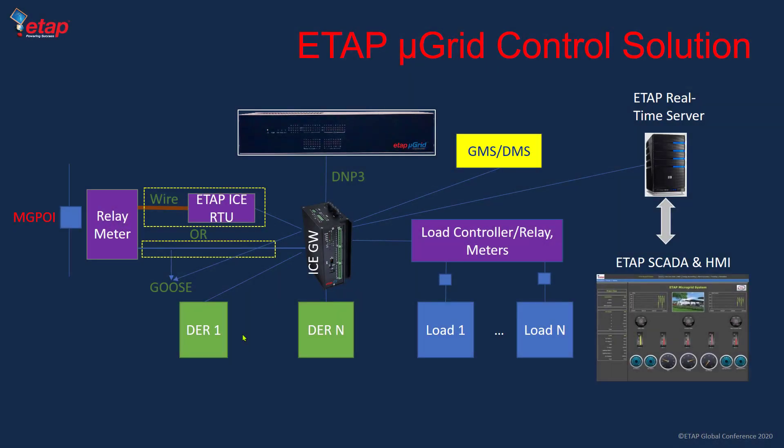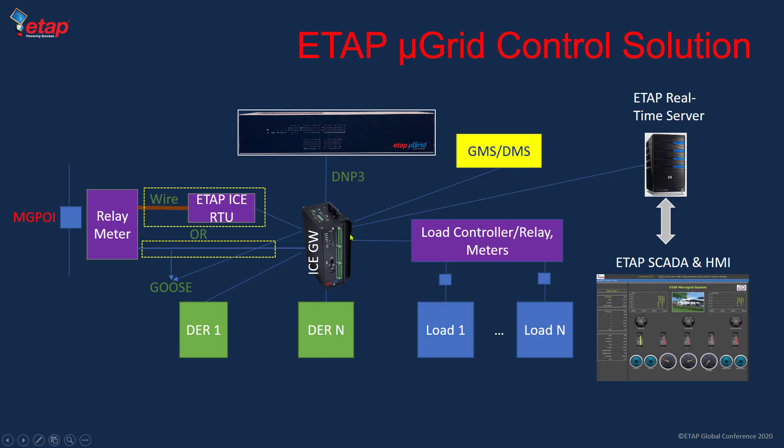The ETAP microgrid control solution includes mainly the ETAP microgrid controller, which is a supervisory controller and a gateway. This ICE gateway has two roles, with dual components where one runs at very high speed and the other runs at lower speed. We can achieve both high speed unplanned islanding but at the same time do dynamic sophisticated logic.